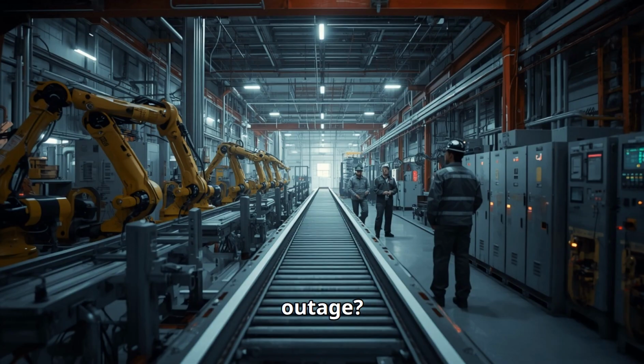What happens during a power outage? Every modern factory depends on electricity. Electric motors drive conveyor belts. Hydraulic pumps provide pressure. Compressors generate compressed air. Robots perform thousands of precise movements every hour. Programmable logic controllers, or PLCs, coordinate every operation. When power disappears, everything stops. Motors lose torque. Production lines freeze. Robots stop wherever they are. Safety systems activate. To someone watching, it may seem like the factory has simply paused.